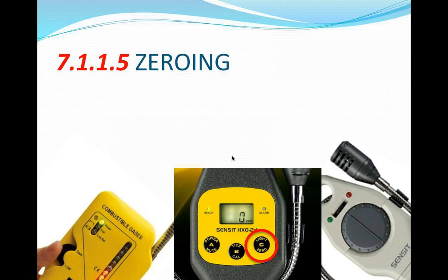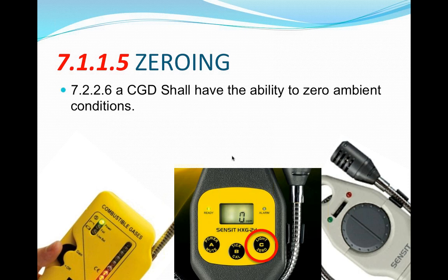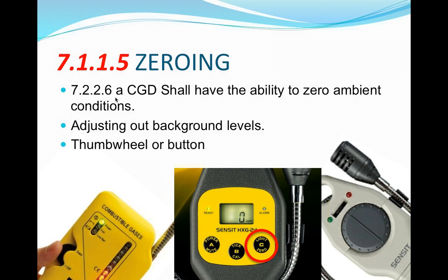7.1.1.5 talks about zeroing of the combustible gas detectors. That's an incorrect number there; 7.2.2.6 is not correct anymore. But we're looking for a combustible gas detector to have the ability to zero in ambient conditions. That means to adjust out for background levels so that you can see as the concentration rises and you're getting to the source, or the heart of where the leak is. And either the thumb wheel or button can be used to zero out the background levels. This adjusts for the threshold, or the same can be done on a digital device to adjust for the digital threshold to zero it.